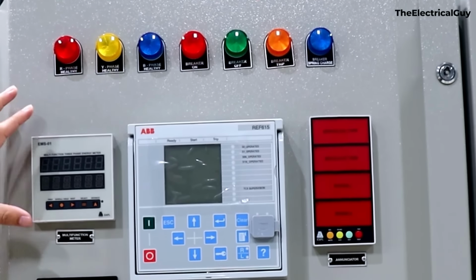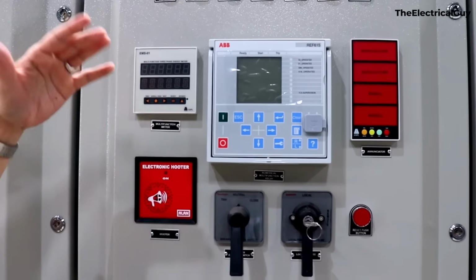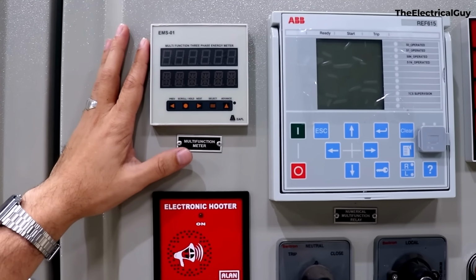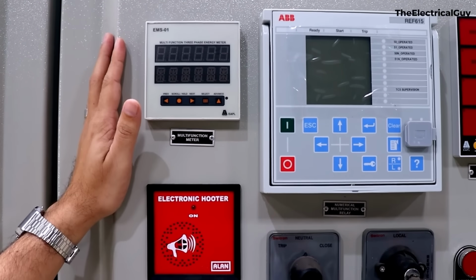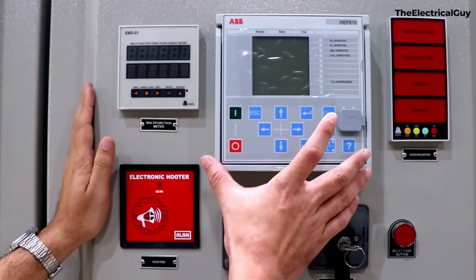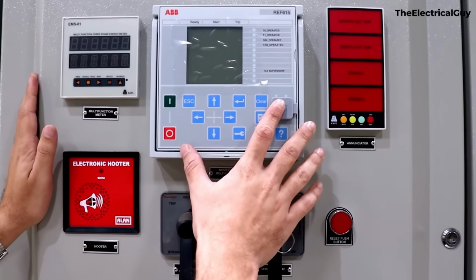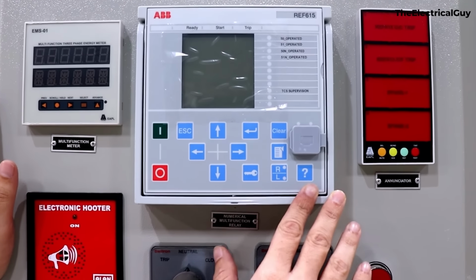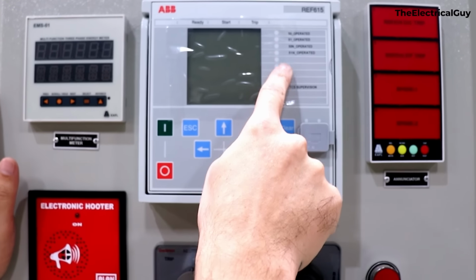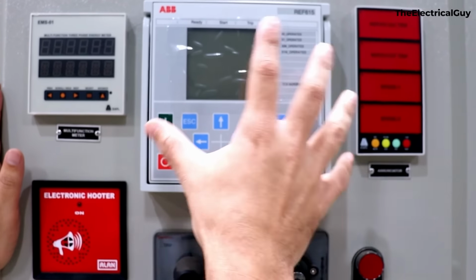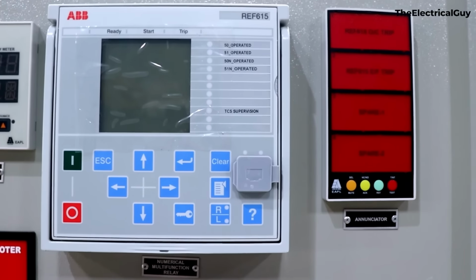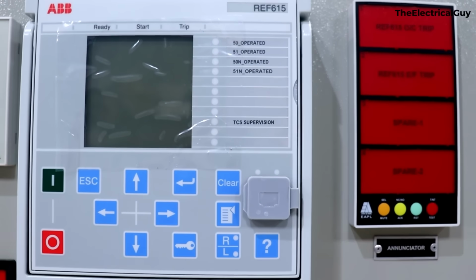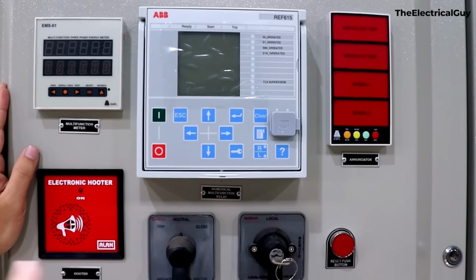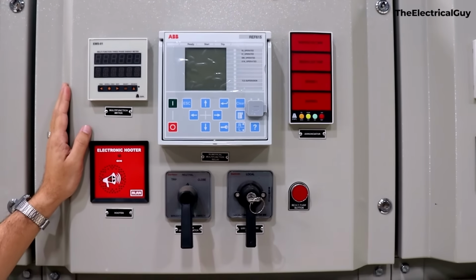And we have a multifunction meter here, which will help us in measuring different kinds of parameters that we have. It will show us all the time. And this is the relay that we have, and it helps us with the different types of protection. You can see the ANSI codes for those are given here, and everything. This is kind of the master relay for this particular panel. So like this, we'll have a relay for all the panels except for the bus riser panel.